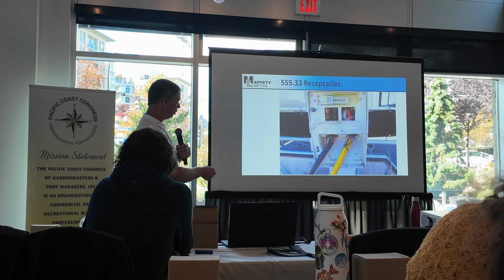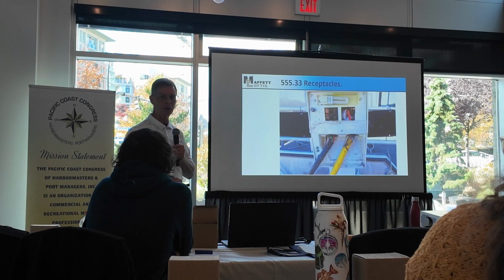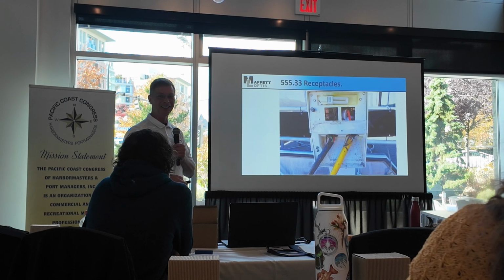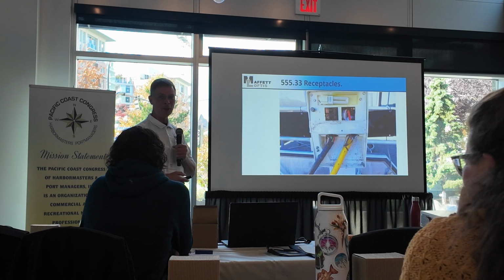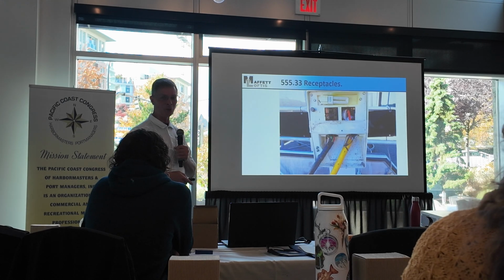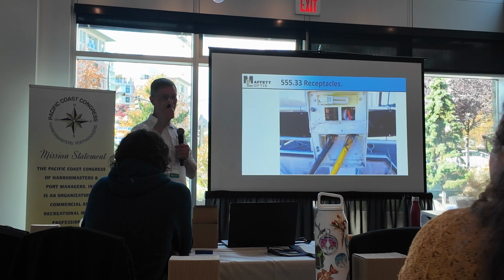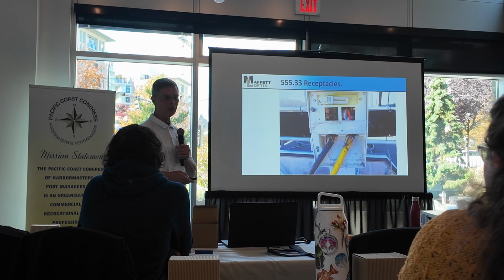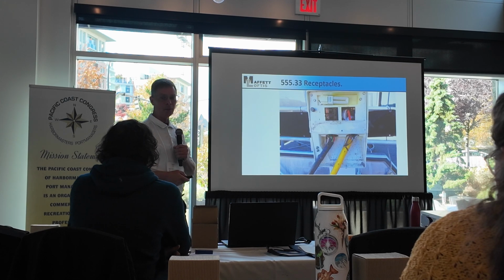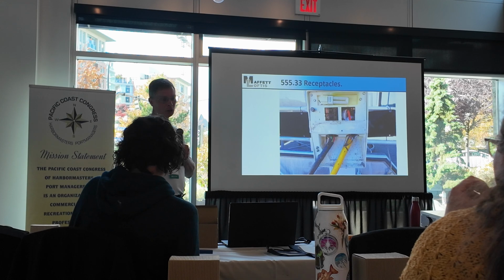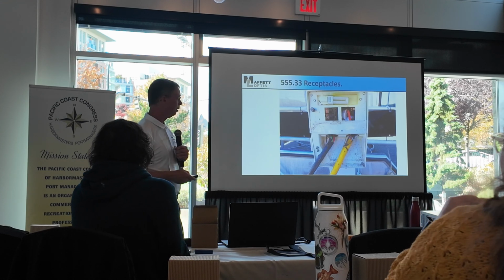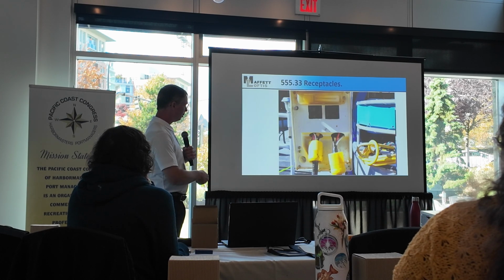Even the breaker is missing on this one, so they're wired right into the bus. Okay? They kept tripping, so they just took the breaker out and remounted it. Like you say, tenants, they do some weird things. They do. Yeah, and you can't let them do this. This is just absolutely a no. Okay? And it happens over and over.